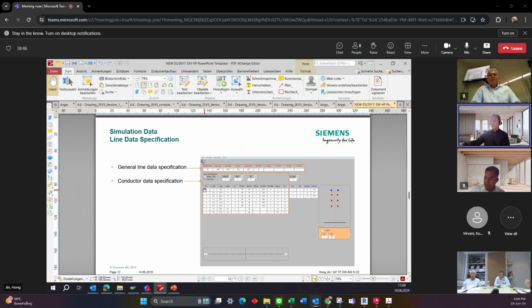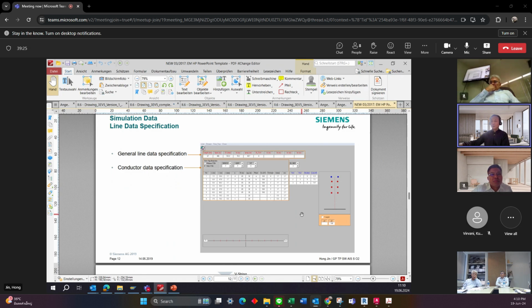Then we have many fields to be filled out with the data from the customer side. We need to have the span dimension. We also need the footing resistance value, and so on. All those data must be provided by the customer with current measurements. As we know, footing resistance changes from year to year due to different soil quality, or even the underground water level, which also influences the footing resistance. And as a reliable basis for the line study, we need the actual data.